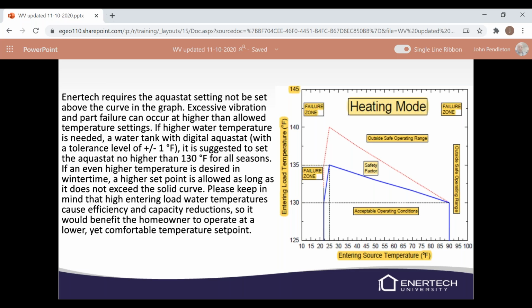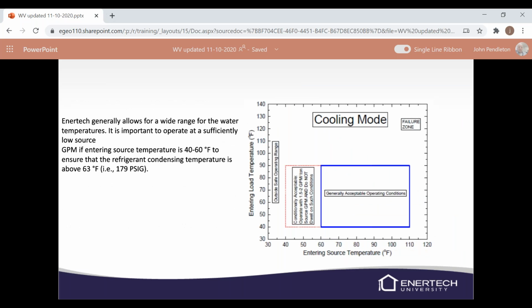So make sure we're setting up our water temperatures appropriately. These heating curves, or this graph, we do list these in the IOM towards the front because we want you to make sure that you're following and staying within the safe operating mode of the compressor. We ran into this a lot back in, I don't know, around 2012 with the WT water-to-water units, guys setting water temperatures at 140 degrees, compressors are failing, and oil's not returning, and acid burnouts, things like that. So just not a good thing. We have one for cooling mode as well, so make sure we're always looking at the safe operating parameters for the compressor. And these are straight from Emerson or Copeland, the compressor manufacturer.